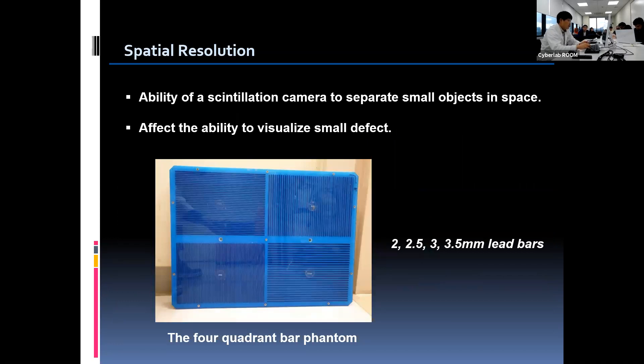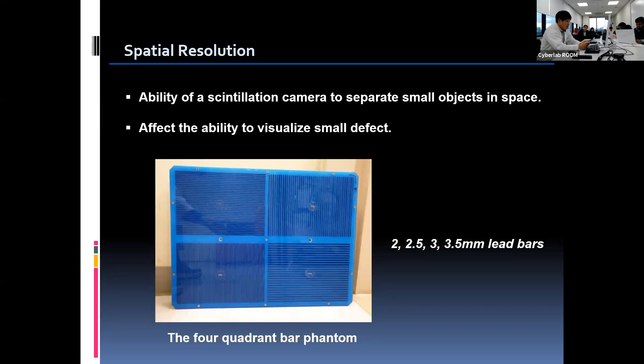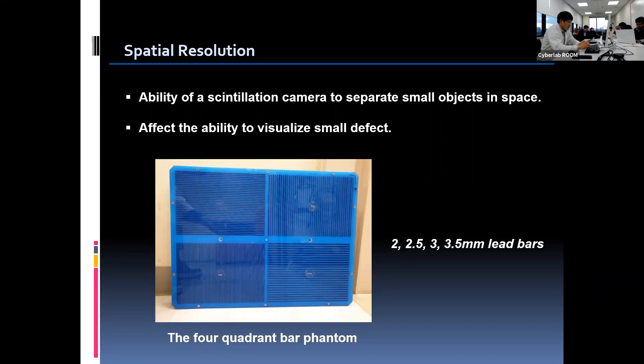The next test is spatial resolution. Spatial resolution is the ability of a scintillation camera to separate small objects in space. Good spatial resolution enables us to see small defects in the clinical patient study. A four-quadrant bar phantom is used for the spatial resolution test with the flood sheet source. Four different widths of lead bars are embedded in each quadrant. The lead bar widths are 2, 2.5, 3, and 3.5 mm respectively.